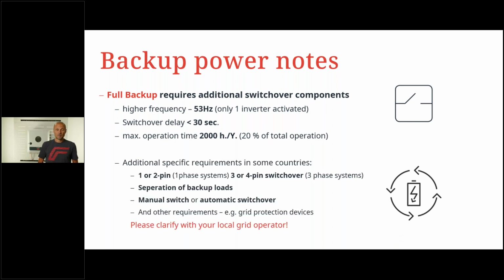Additionally, there are specific requirements in some countries. On the Primo range, single phase, you will have a 1 or 2 pin switchover, and in a 3 phase, a 3 or 4 pin switchover. So depending on the country, in some countries you need just to switch the phases. In other countries you also need to switch the neutral. So there are these two different options. Do you need to switch the neutral or not, basically?